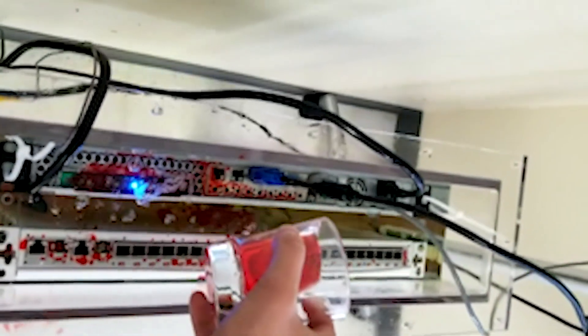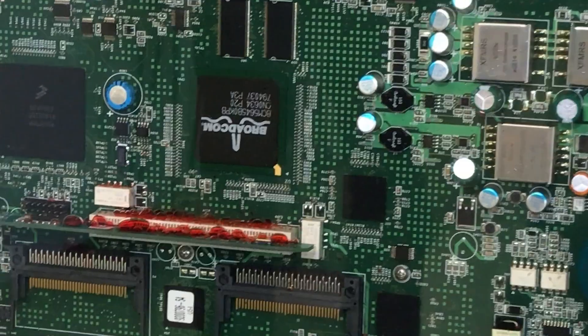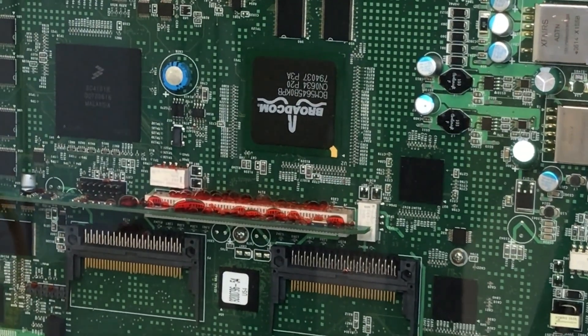As you'll see in the video, the water droplets cascade down the front of the server as in a pachinko machine. However, the net effect was nothing. The server was fully protected from the water by the EC100 coolant. Even though the water pooled on a number of the components, the server continued to operate just fine, as did the network switch.